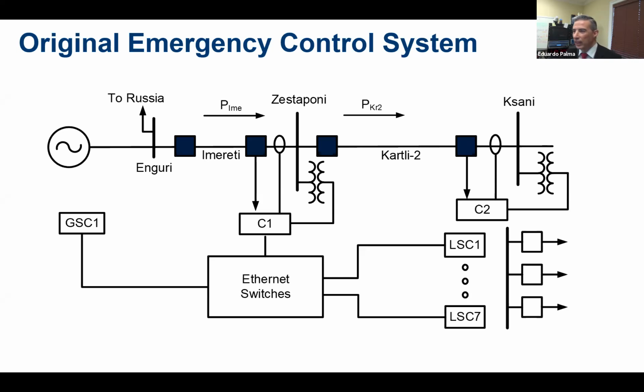Thank you, Vladimir. One important thing that I wanted to mention to complement your comments is that the original Ethernet network that was already installed or existing, in order for these substations to communicate with each other, or for the devices that are measuring the power system and then making logical decisions, was used and was implemented within 4 months. So it is very important to mention that if an Ethernet or fiber optic communication network is not existent, then it will be very tough to implement this type of messages, Ethernet messages that are sent in milliseconds, so that a remedial action or an emergency control action takes place.